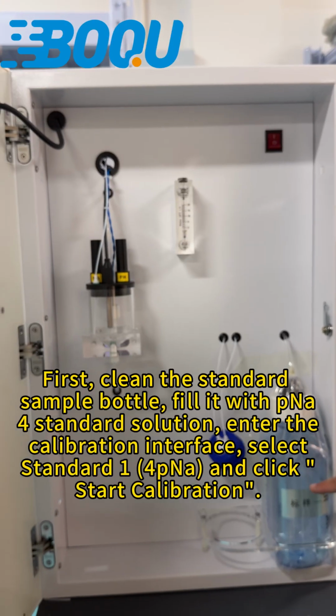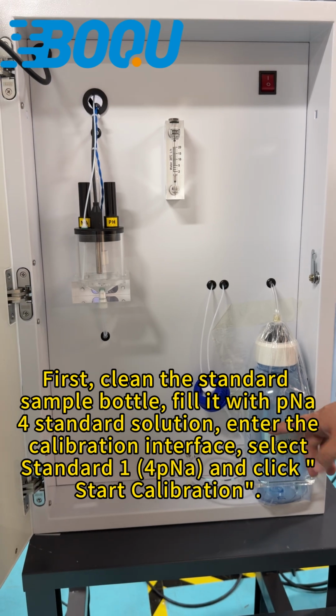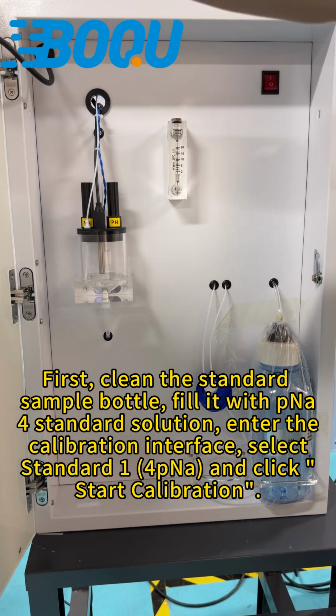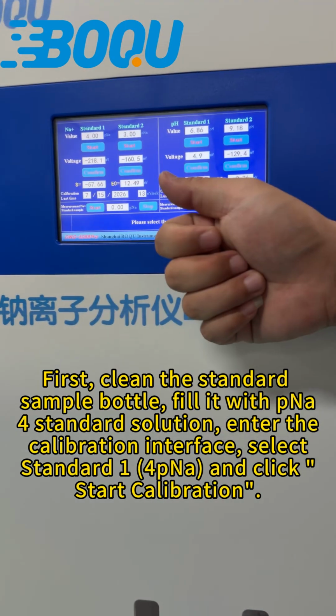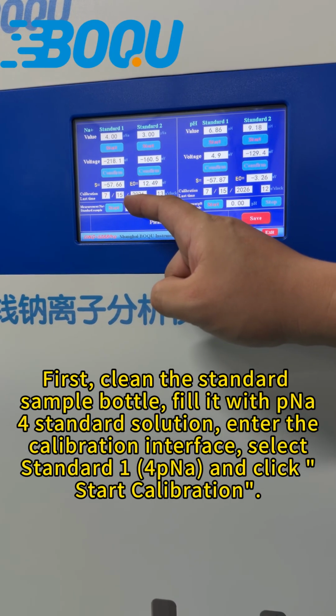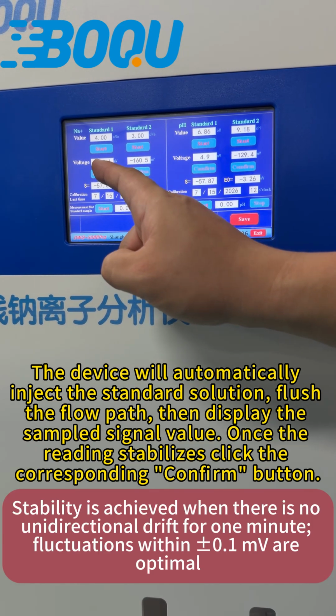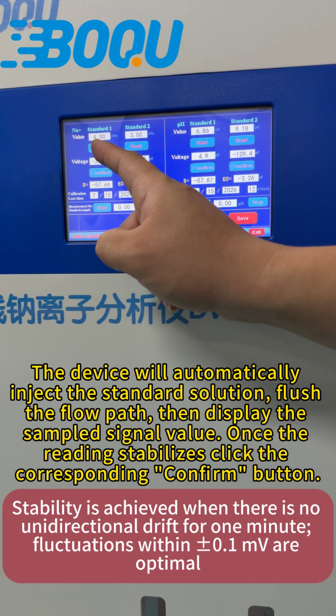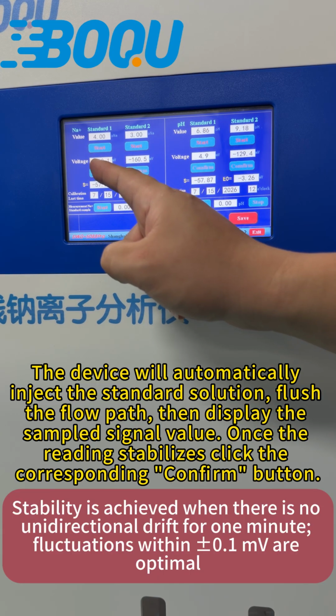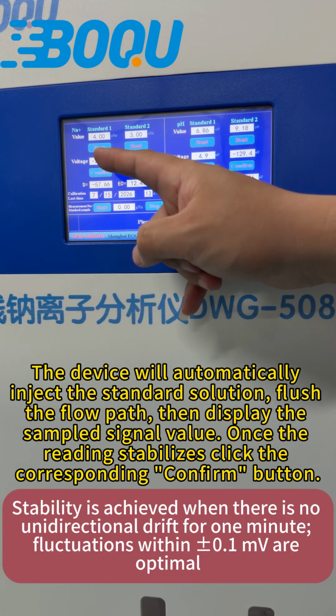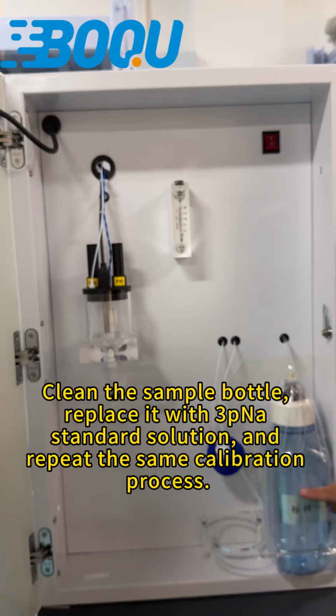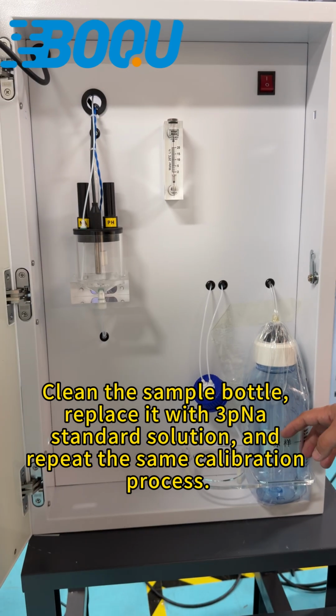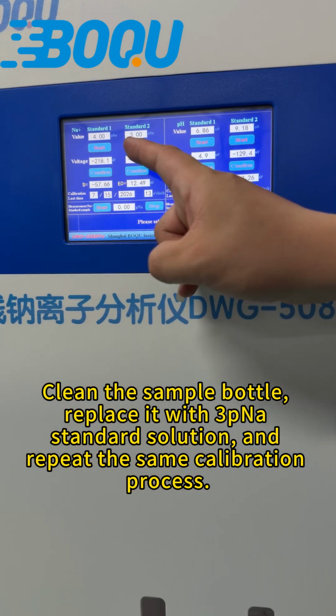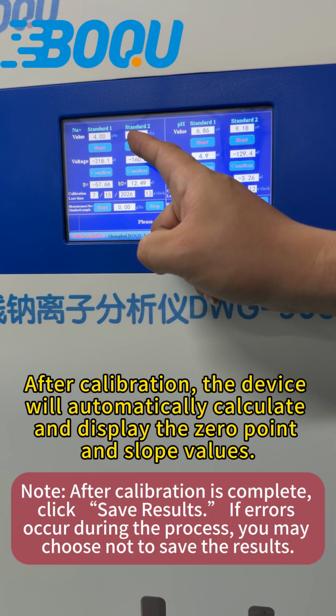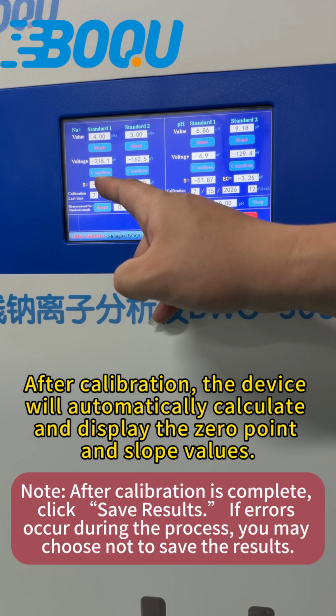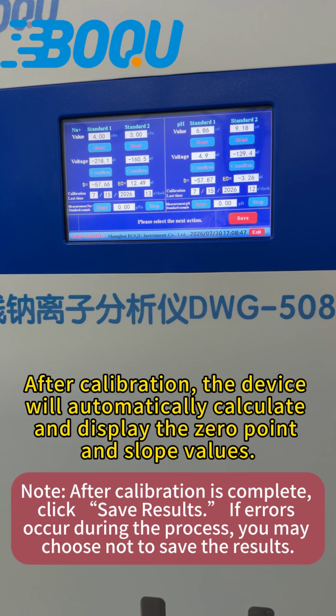Calibration section. First, clean the standard sample bottle. Fill it with pNa standard solution. Enter the calibration interface. Select Standard 1, 4 pNa, and click Start Calibration. The device will automatically inject a standard solution, flush the flow path, then display the sampled signal value. Once the reading stabilizes, click the corresponding Confirm button. Clean the sample bottle, replace it with 3 pNa standard solution, and repeat the same calibration process. After calibration, the device will automatically calculate and display the 0 point and slope values.